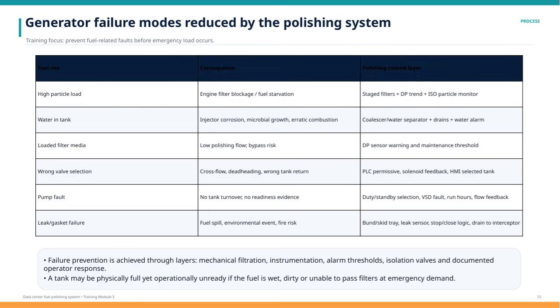Pump faults can cause no tank turnover or readiness issues, so duty and standby pump selection, variable speed drive fault detection, run hours monitoring, and flow feedback are critical controls. Finally, leaks or gasket failures can result in fuel spills or fire hazards. We manage this risk with containment structures like bunds and trays, leak sensors, automatic stop and close logic, and drainage to interceptors. The important takeaway is that failure prevention is a layered approach.